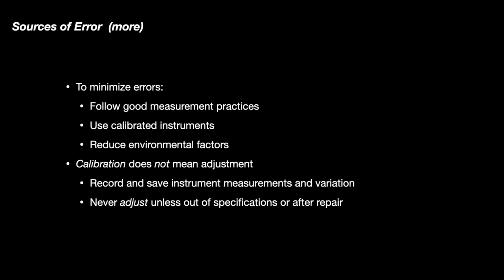Much of the equipment you see around here came into my hands because it was considered more expensive to calibrate than to buy new. That's unfortunate, because I'll make a pitch for older equipment. Number one, it's easier to work on because it's not surface mount, it's through-hole in most cases. Some newer equipment, and by newer I mean 21st century as opposed to 1989, 1990 vintage, has self-calibration routines built in. Others you've got to go in and make adjustments if necessary.